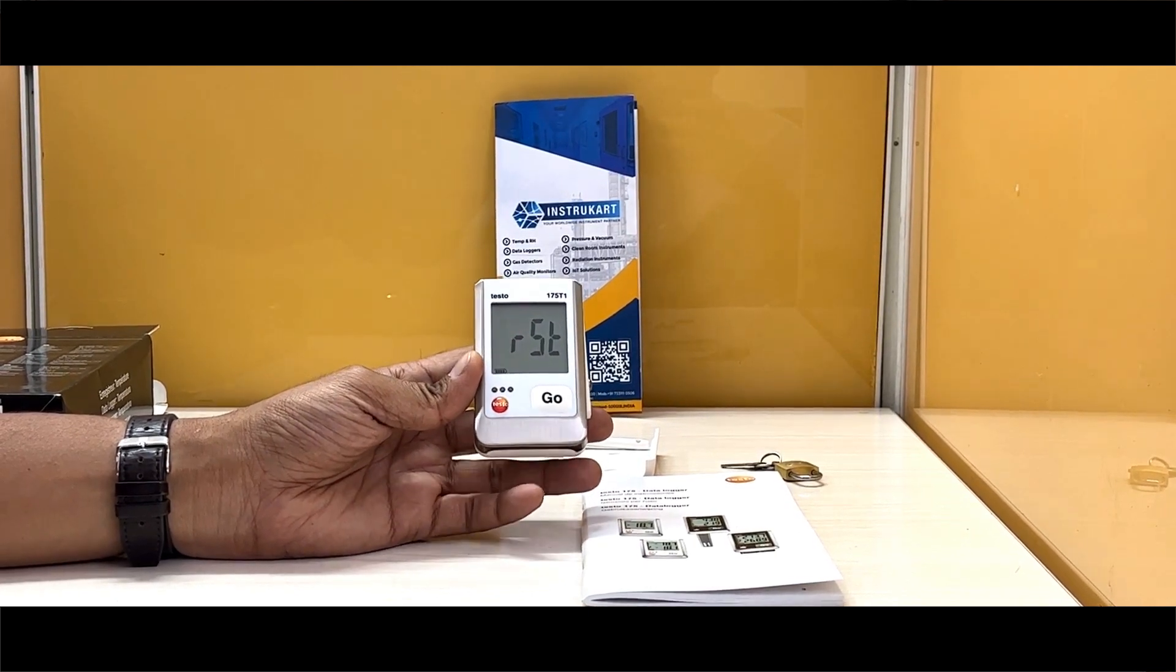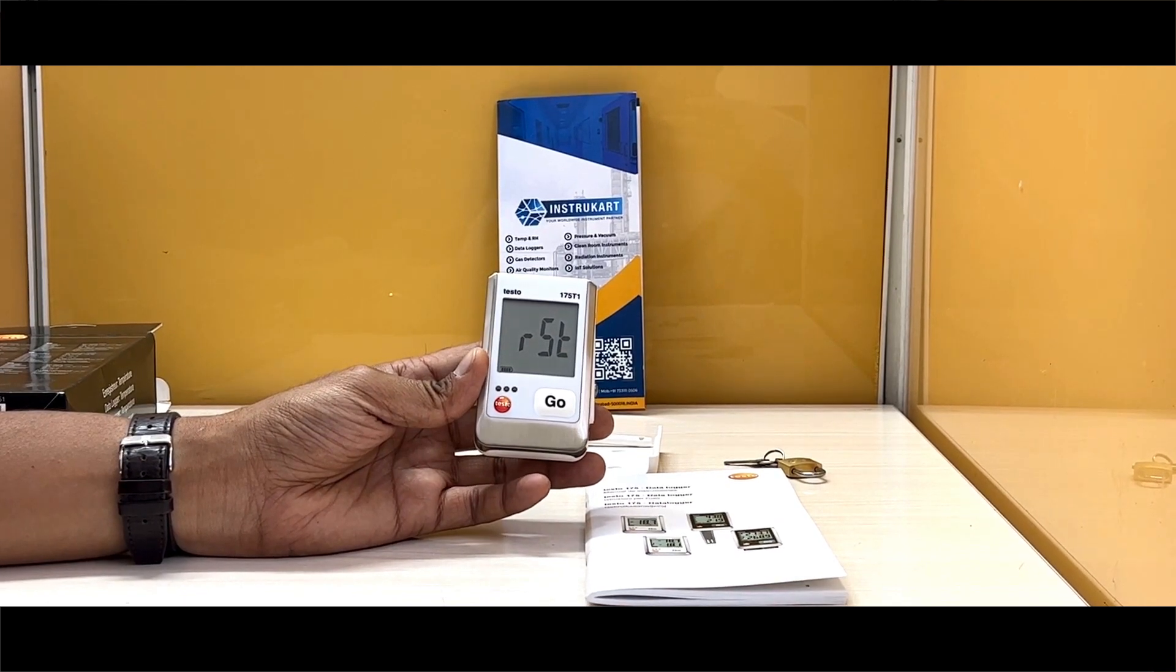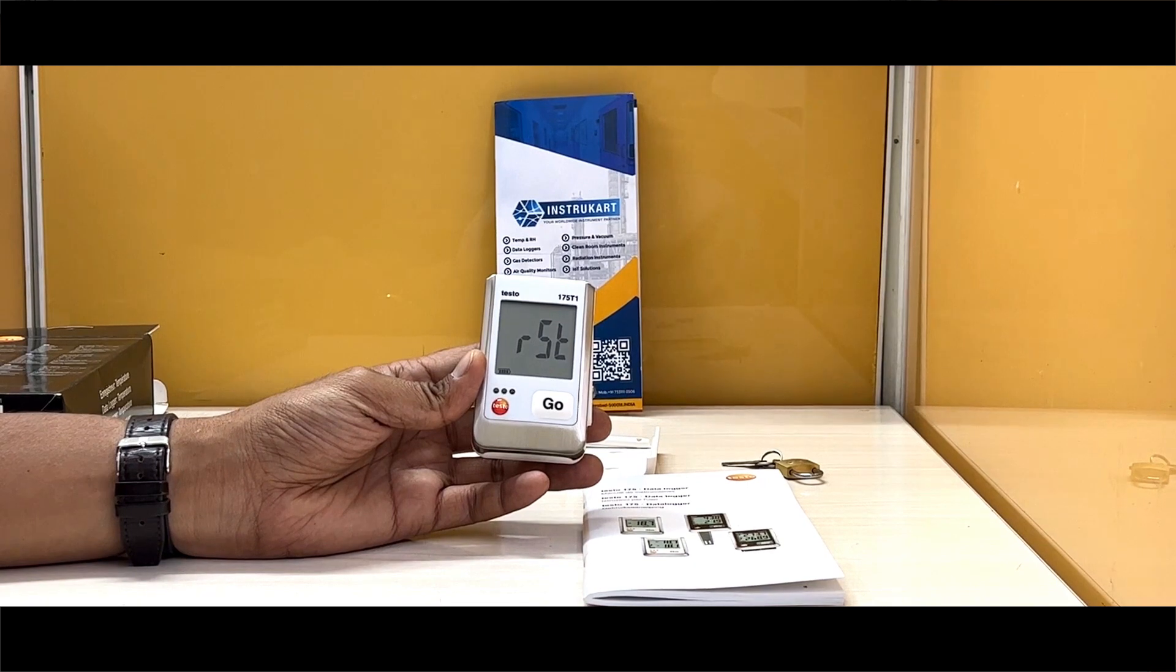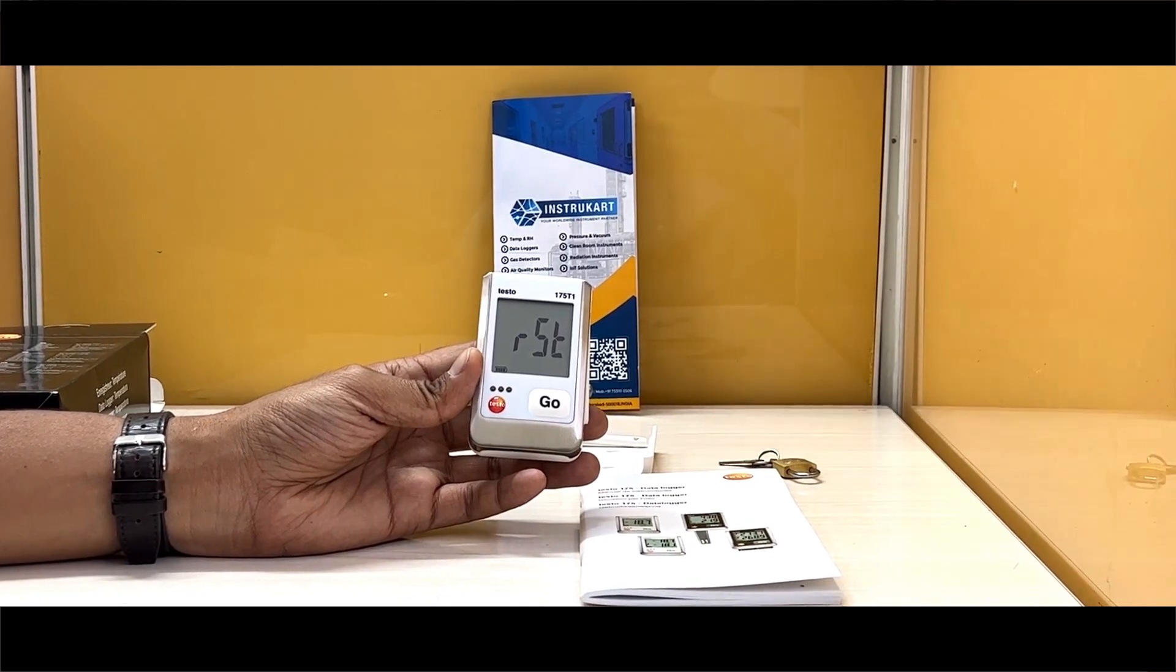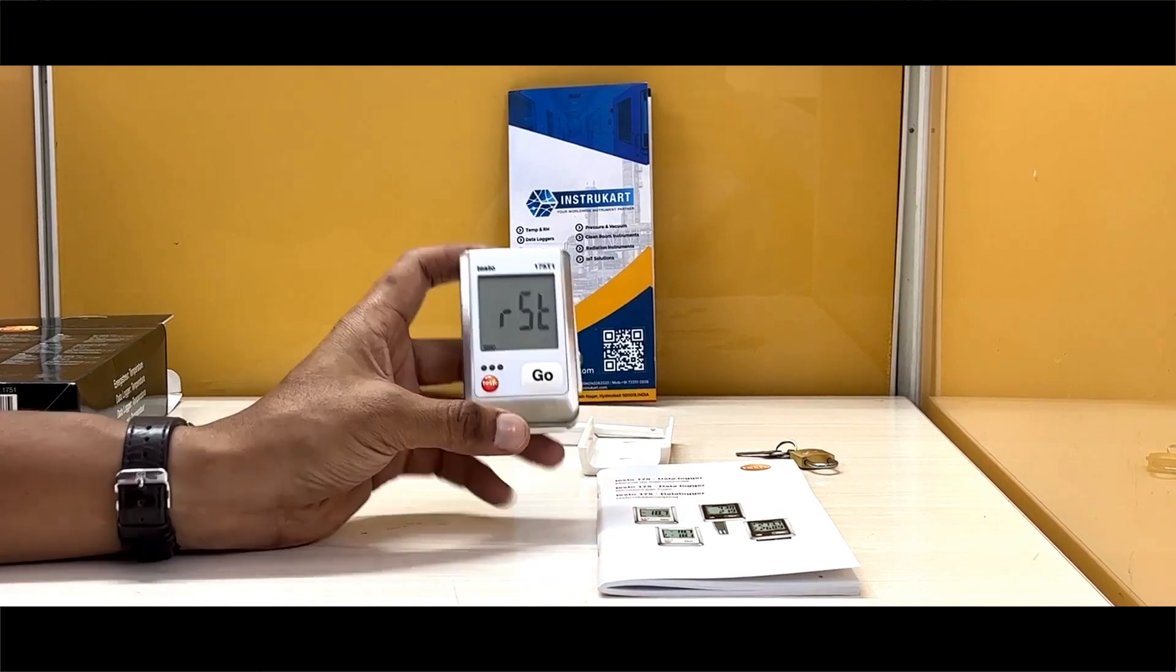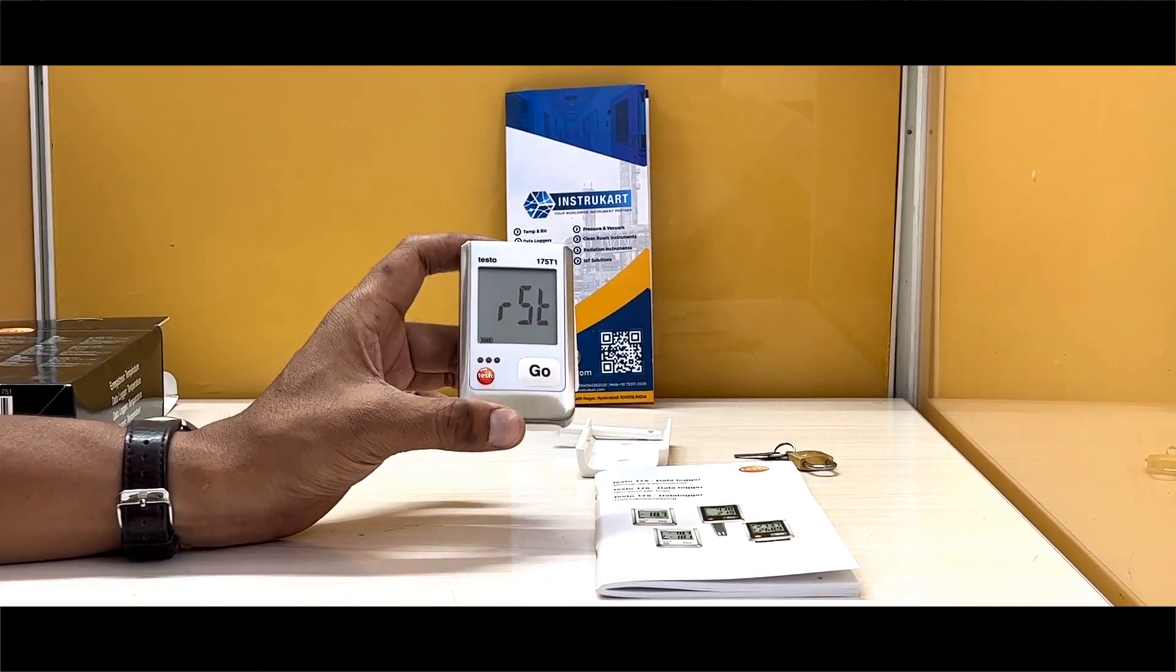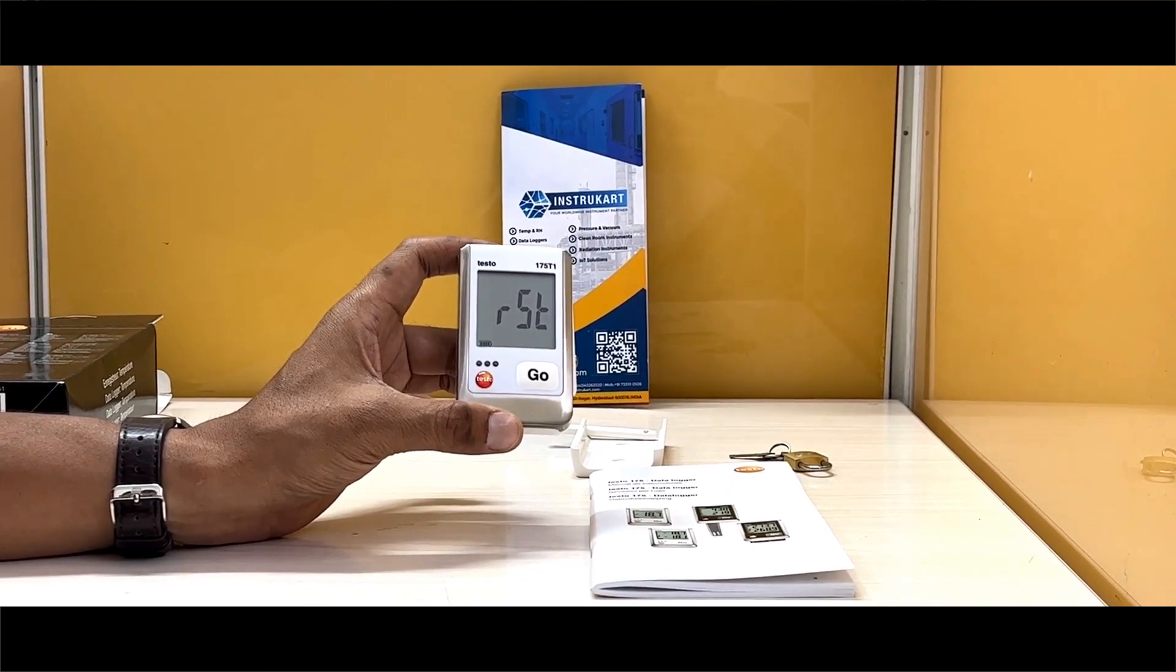The range for this data logger is minus 35 to 55 degrees Celsius with a resolution of 0.1 degrees Celsius and an accuracy of plus or minus 0.4 degrees Celsius. It has a data logging option which can capture up to 1 million readings, and the measuring rate could be 10 seconds to 24 hours.